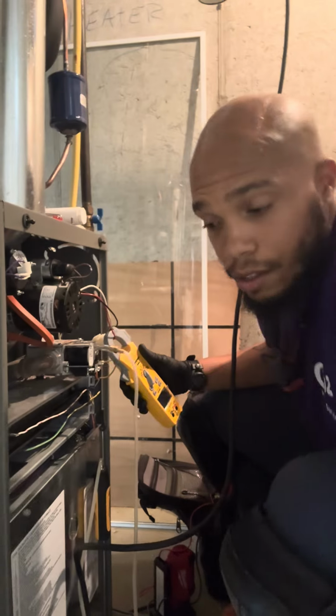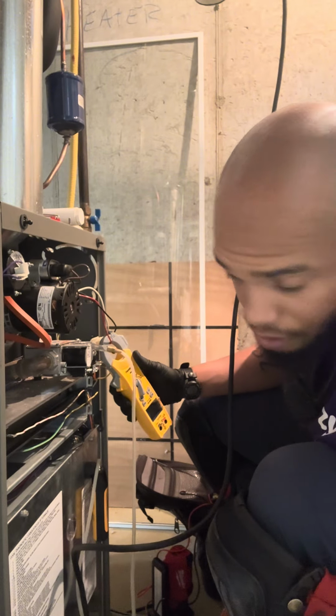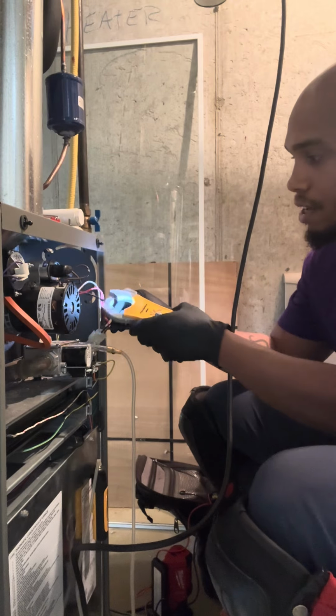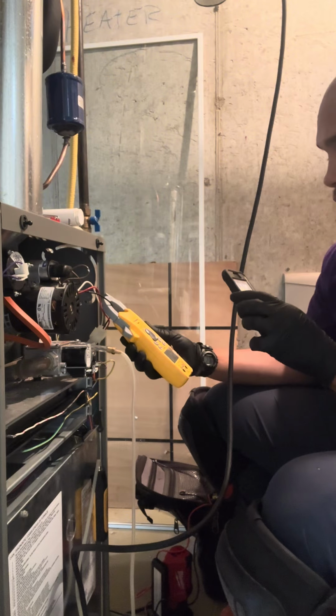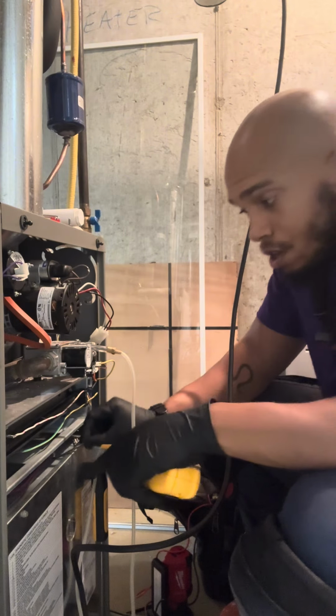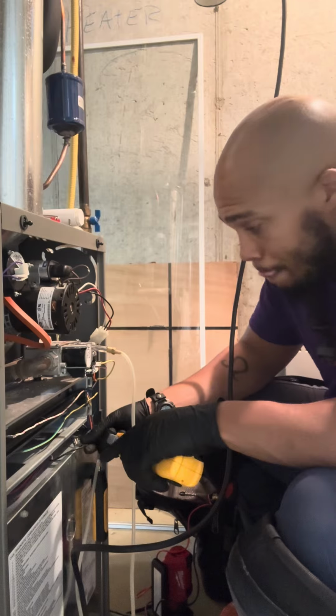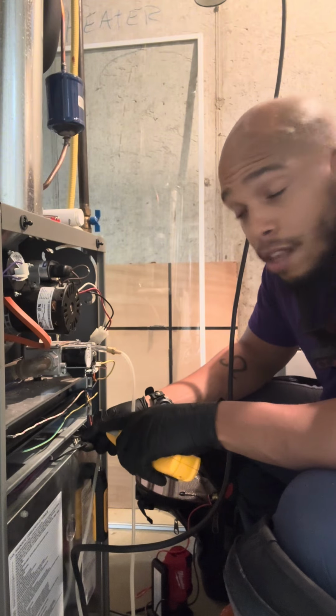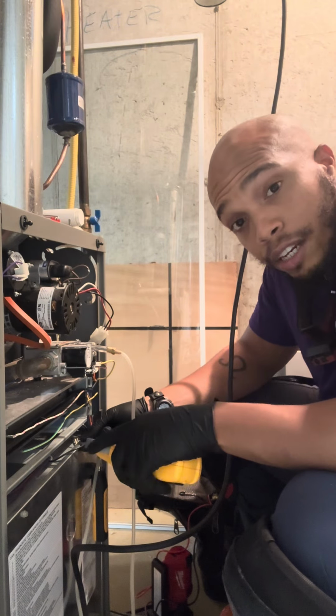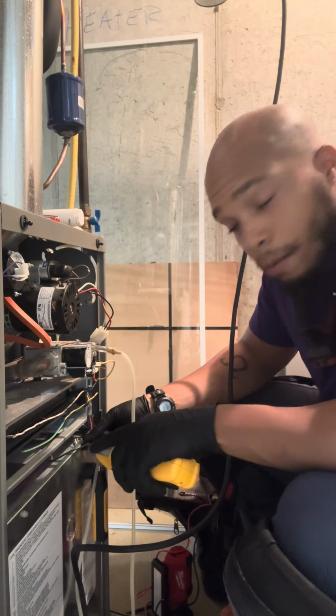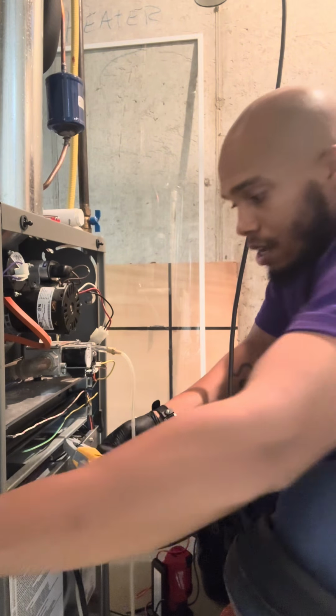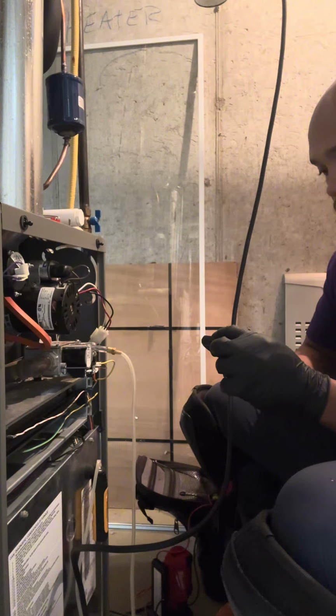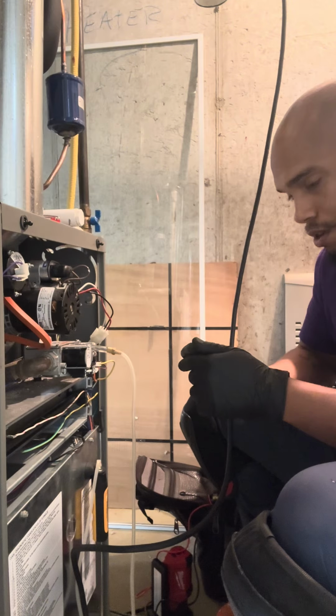Blower's kicking on. Flames look good to me. All right, let's go ahead and start our combustion analyzer. Check our second stage inducer amps. Those are looking good as well. Now I'm going to latch onto the high voltage line, and I'm going to check the total system amps. All I had to do is subtract the inducer motor amps, and that gives me my blower motor amps. Blower motor amps look good. I like it. Let me check my phone, my manometer pressures. Those are good.